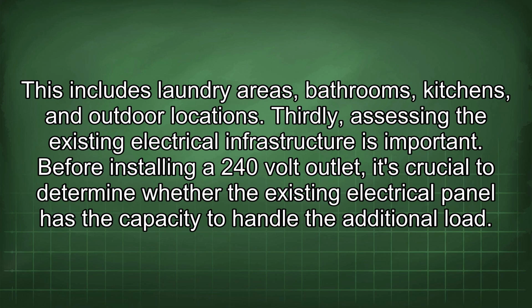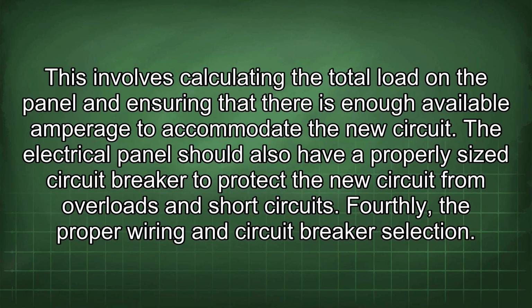Thirdly, assessing the existing electrical infrastructure is important. Before installing a 240 volt outlet, it's crucial to determine whether the existing electrical panel has the capacity to handle the additional load. This involves calculating the total load in the panel and ensuring that there is enough available amperage to accommodate the new circuit. The electrical panel should also have a properly sized circuit breaker to protect the new circuit from overloads and short circuits.